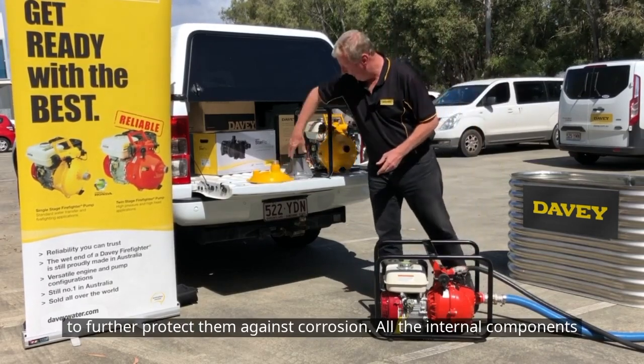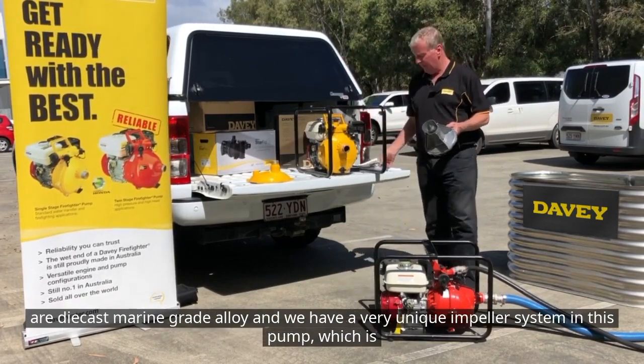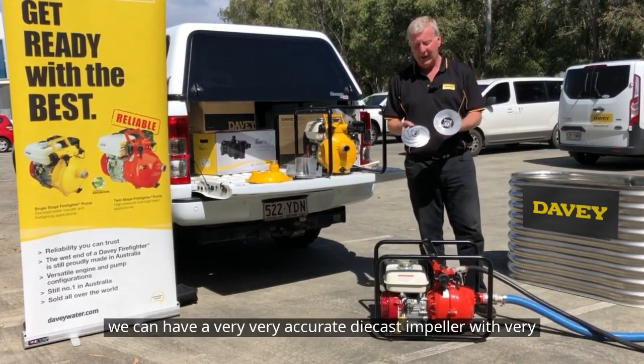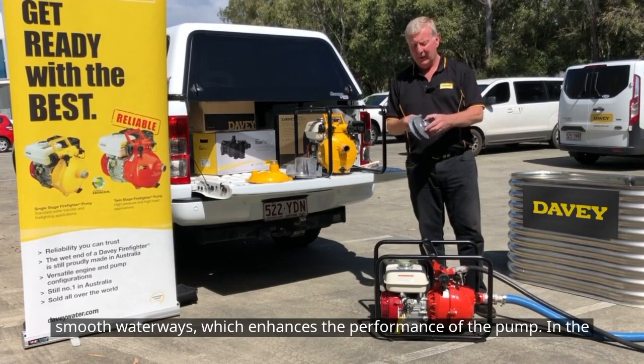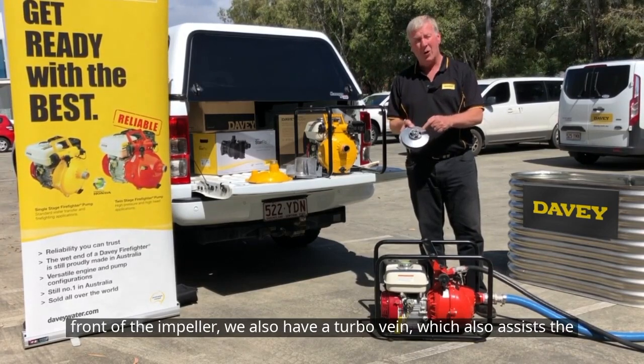All the internal components are die cast marine grade alloy, and we have a very unique impeller system in this pump, which is actually a clamped impeller arrangement. It consists of two pieces. This way we can have a very accurate die cast impeller with very smooth waterways, which enhances the performance of the pump. In the front of the impeller, we also have a turbo vane, which assists the pump's priming ability.